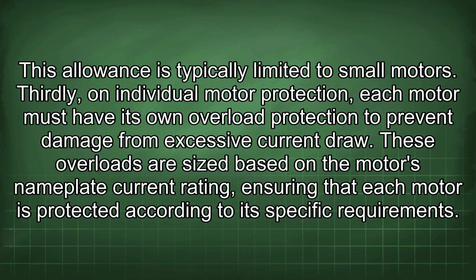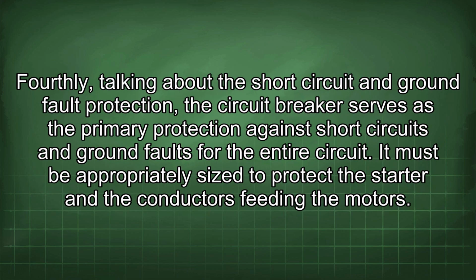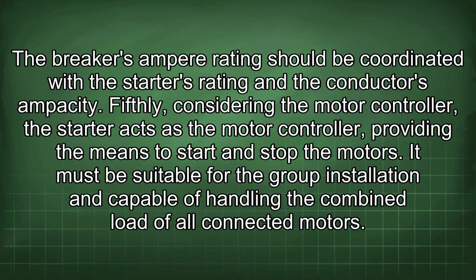specific requirement. Fourthly, talking about the short circuit and ground fault protection, the circuit breaker serves as the primary protection against short circuits and ground faults for the entire circuit. It must be appropriately sized to protect the starter and the conductors feeding the motors. The breaker's ampere rating should be coordinated with the starter's rating and the conductor's ampacity. Fifthly, considering the motor controller, the starter acts as the motor controller, providing the means to start and stop the motors. It must be suitable for the group installation and capable of handling the combined load of all connected motors.